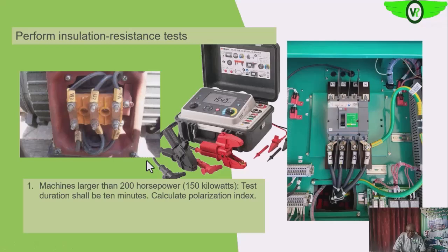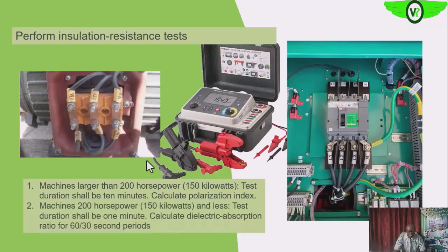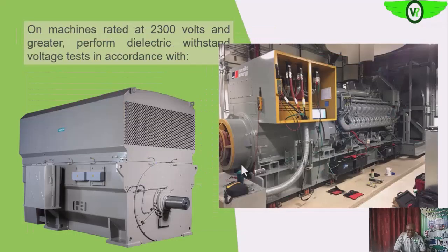So for equipment that are larger than 150 kilowatts, we should carry out the test for up to 10 minutes, okay, so that we'll be able to calculate the polarization index. If the machine is less than 150 kilowatts, we can test for 30 or 60 seconds, and then we calculate the dielectric absorption. All of these are done to ascertain the integrity of the insulation of either the electric motor or the generator. On larger equipment, you perform the dielectric withstand voltage test.